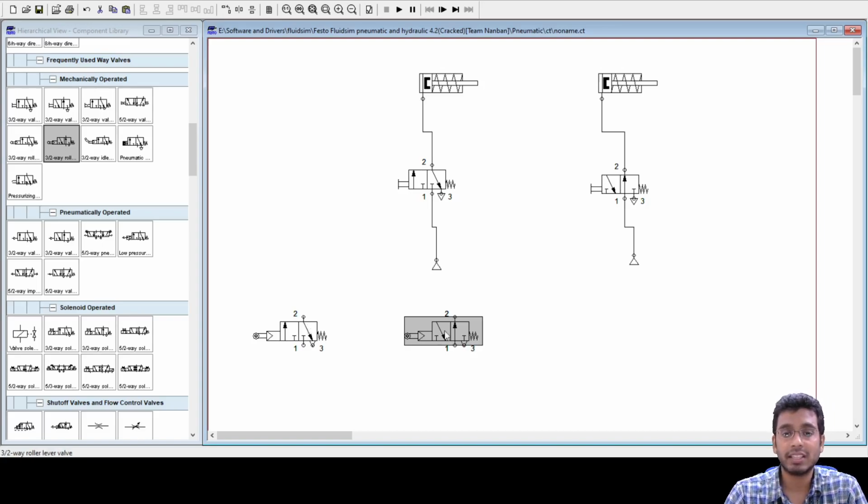In this case, technically, when the valve is not actuated, you will have your pressurized line connected to this port number 2, and the moment the valve gets actuated, that would result in this supply getting cut off. Fine. So it depends. In the use we had, we wanted to use only a normally closed valve, so that our actuation only triggers some other movement.